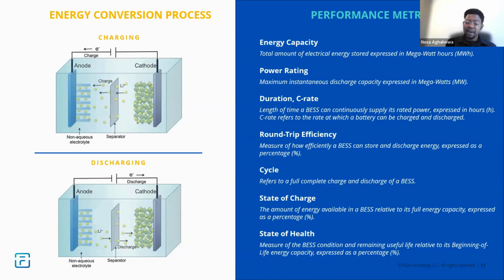Batteries degrade when internal resistance builds up within the cell and inhibits the flow of positive ions through the electrolyte. Things like time, temperature, and the way we operate the battery can cause this internal resistance to build up and degrade the battery. The state of health is just a measure of the remaining useful life of the battery.